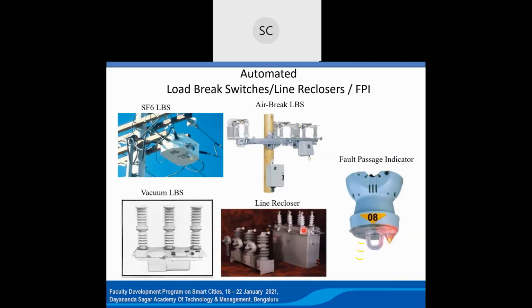See, some sectionalizers will be getting power supply through RMU or different feeders and get connected, disconnected. And those sections that are healthy within that small network will get their power from the alternate, in the combination of auto recloser, sectionalizer, RMU. Only the small section where that permanent fault is there, those customers are affected, and the crew has to come and see that. Location is also easier, and only that particular segment or area, a very limited number of consumers, gets affected. This is how that auto recloser works in tandem with the sectionalizer.